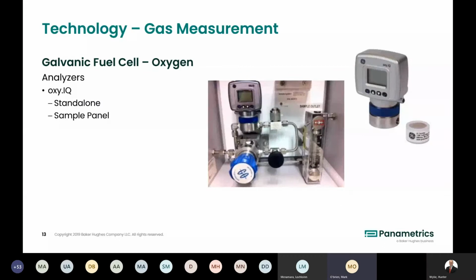You want to move on a little bit. Again, you can see the OxyIQ here with the corresponding cell to the right. The sample system can be very compact if required, or it can be customized as required. So if you have a requirement for a sample system with 5 transmitters in there with displays, this is not an issue. We provide all of these. Again, we provide a standalone or a standardized sample system or customized sample system. Supply is 24 volts and it's a loop powered transmitter, so it has a 4 to 20 output. The same 2 wires that power the unit also provide the signal.